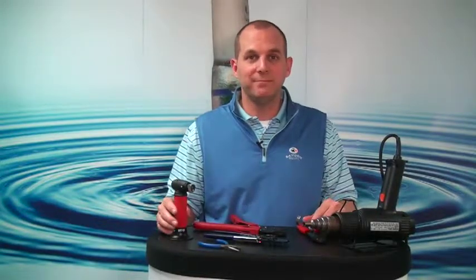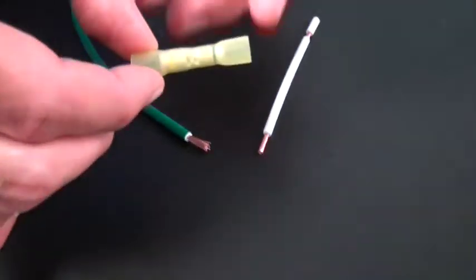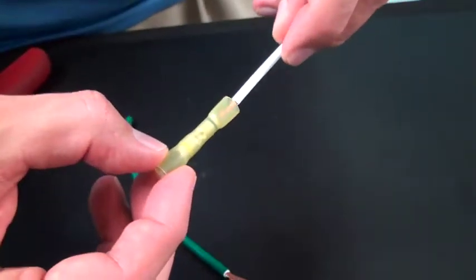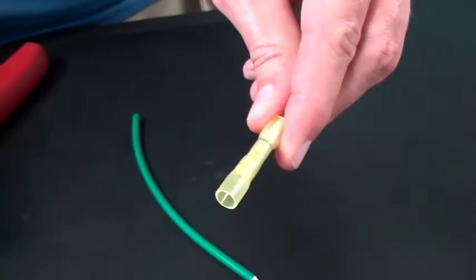Now let's get to the installation. This connector is a unique step-down butt connector that allows you to join two different wires together. First, I'll insert a 16 gauge wire into the barrel with the blue stripe, making sure that I can visibly see the ends of the wire in the terminal's window.